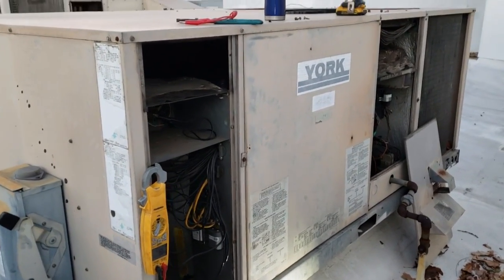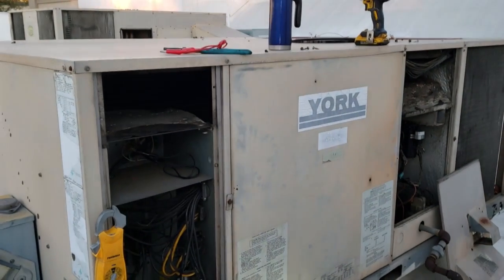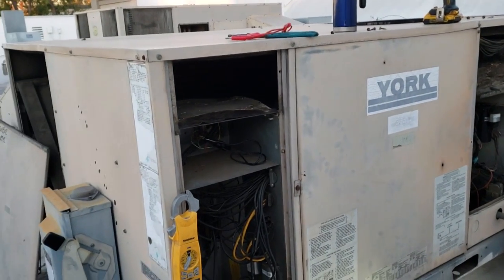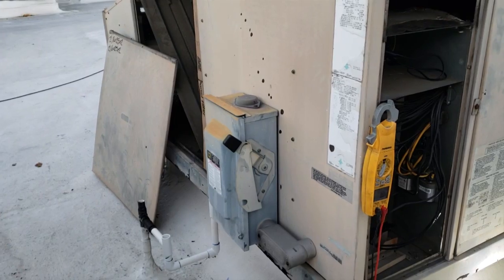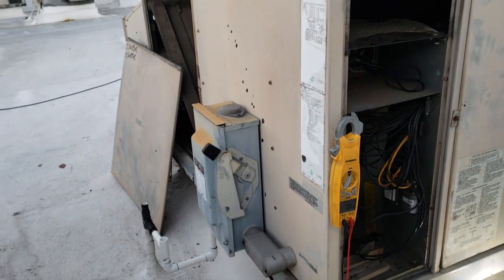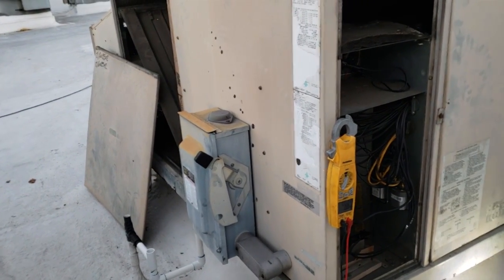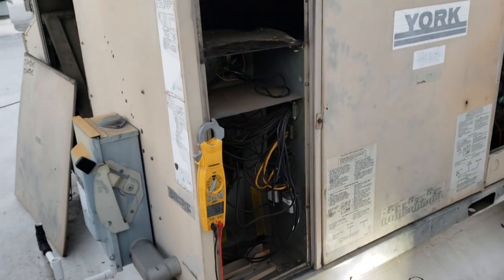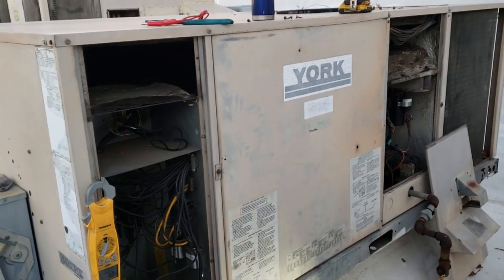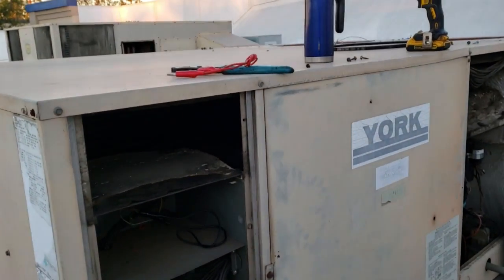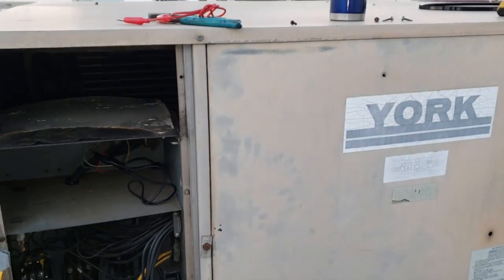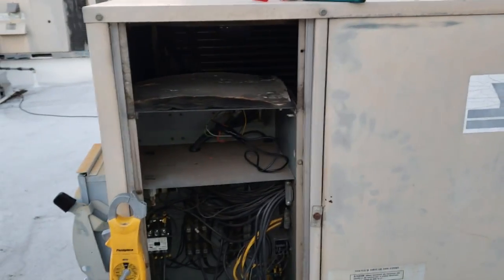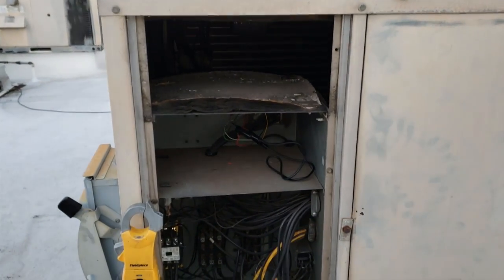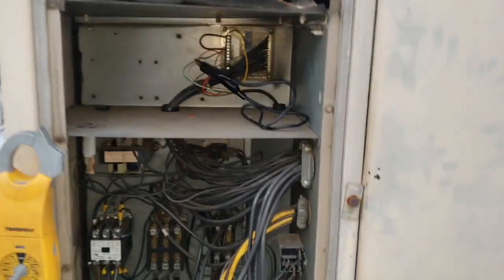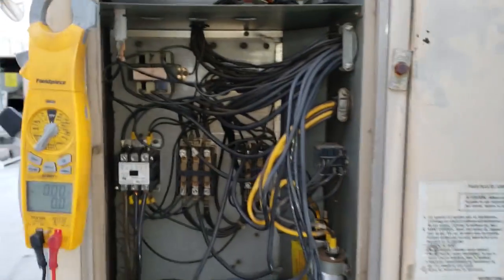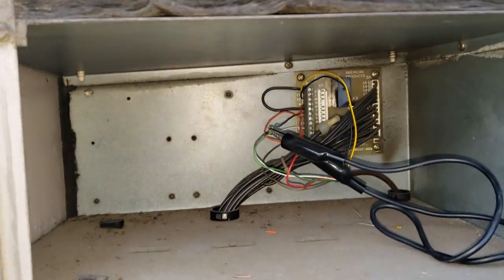Okay, now we're on to the next unit. I tightened up the belt on this one and checked everything. I checked 3-phase power to the disconnect first. It was shut off. Checked the disconnect load side to ground, nothing. Checked all the contactors to ground, nothing. De-energized the unit. I spun all the motors, pulled the bottom of the motor, and inspected everything. Energized the unit and fired up the indoor blower motor with jumpers right now. Indoor blower motor's running fine and amping fine. It's not over amping.